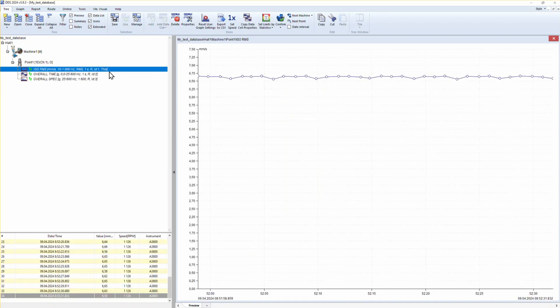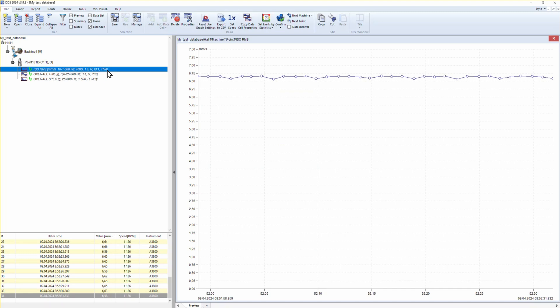Machine is considered as not running until this one data cell, marked as threshold data cell, measures values higher than set threshold. From that moment, values are saved in all data cells according to data saving parameters set.